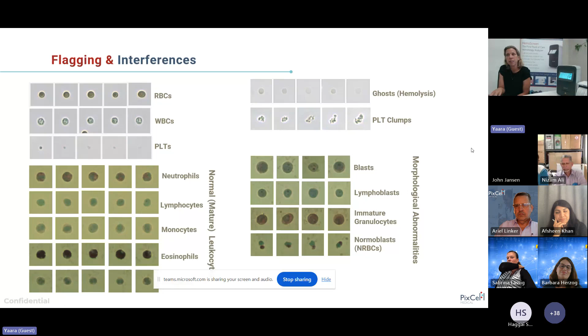staining properties. On the right panel, you see different interferences that are very common in hematology. For example, here on this lane, you see pictures of ghost cells. Ghost cells represent a situation which is, of course, not a good situation, where the blood goes through hemolysis, and this is a very common pre-analytical failure or problem in hematology. So you can differentiate easily between these red blood cell ghosts and the normal red blood cells. And we can just create a flag or an error code if the HemoScreen encounters this interference.